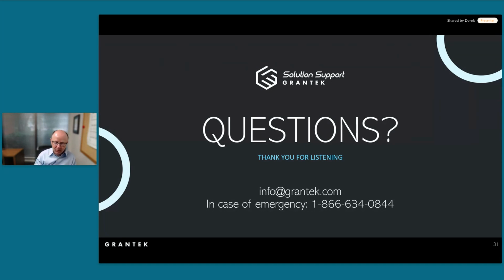So again, we had to pull in some teams and modify the PLC code, modify the wiring, and get it going, because it wasn't a one-to-one replacement. Whereas if that was scheduled ahead of time, it would have been a lot easier. Or even if it was prepped ahead of time, the customer could have saved a lot of downtime.